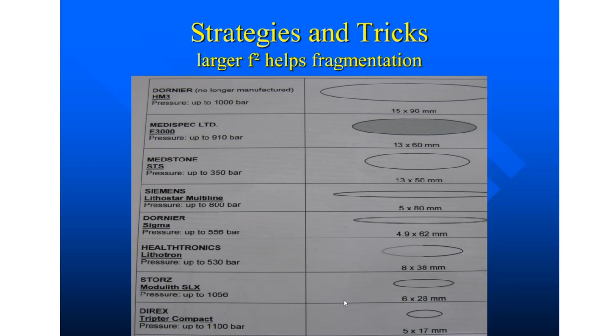When we look at some of the earlier units, we see that we can break it down into volume and peak pressure. Again, the HM3 sort of got it right. It allowed us to have a large volume of energy at F2, a large F2 focus, and we could use lower energy and not get into as much trouble with renal damage as if we might have gone over to the Storz unit, which had a very, very small F2, requiring us, in order to break stones, to use higher peak pressures. And again, that ran the risk of potentially requiring us to do more shock waves and potentially higher energy, potentially causing damage to the kidney.